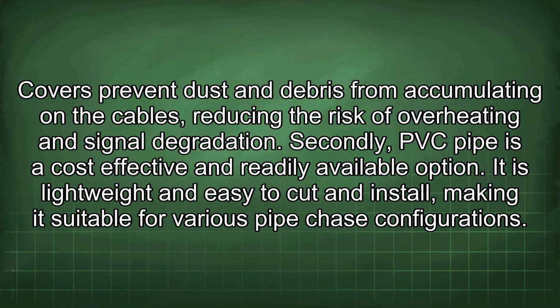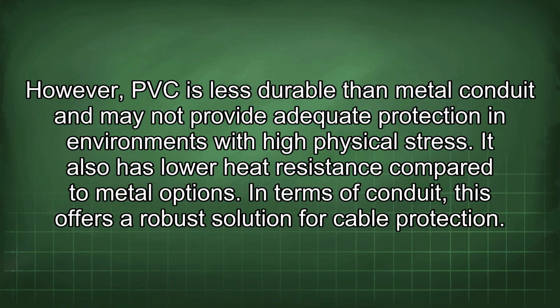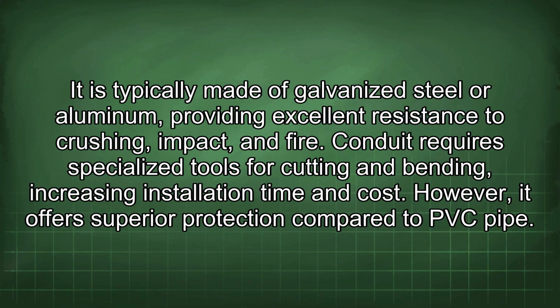Secondly, PVC pipe is a cost-effective and readily available option. It is lightweight and easy to cut and install, making it suitable for various pipe chase configurations. However, PVC is less durable than metal conduit and may not provide adequate protection in environments with high physical stress. It also has lower heat resistance compared to metal options. In terms of conduit, this offers a robust solution for cable protection. It is typically made of galvanized steel or aluminum, providing excellent resistance to crushing, impact, and fire. Conduit requires specialized tools for cutting and bending, increasing installation time and cost. However, it offers superior protection compared to PVC pipe.